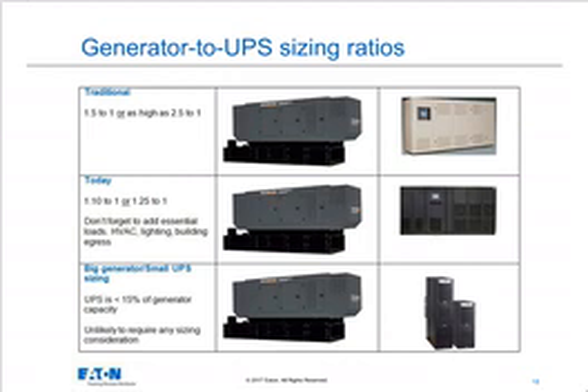Well, not exactly. I'm comparing the generator's output rating to the input power drawn by that UPS, which is going to be a little bit more than 100 kW due to the inefficiency of the UPS. So the things to compare for this ratio, when you see these ratios, is we're comparing the output of the generator to the input power of the UPS.